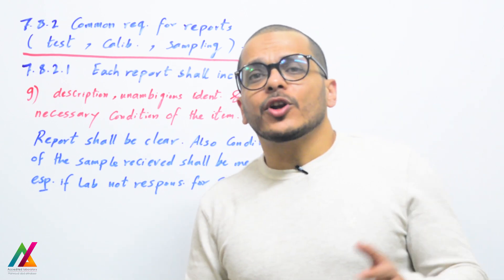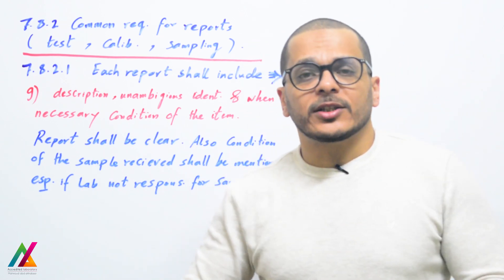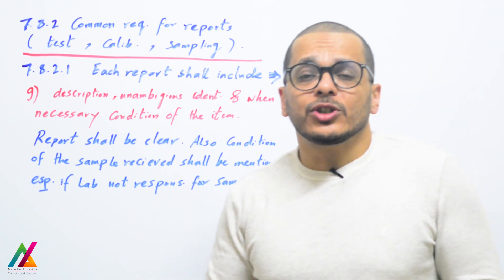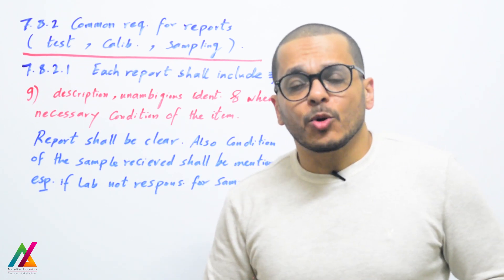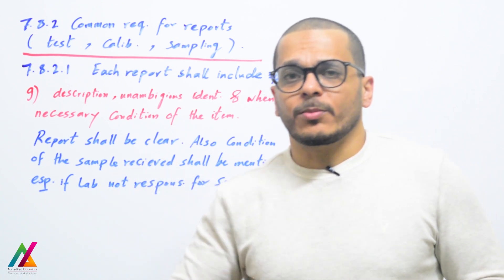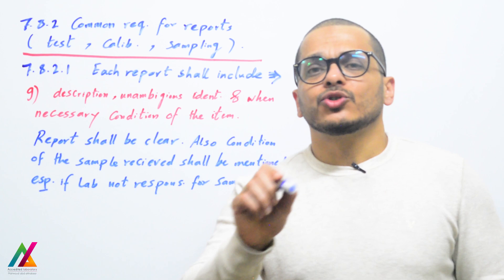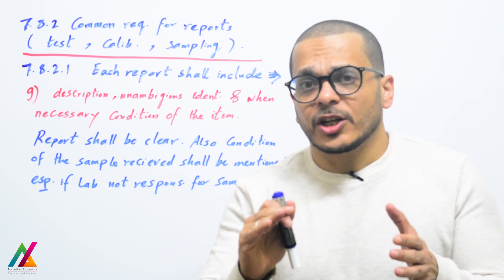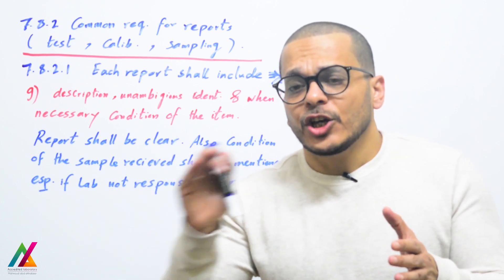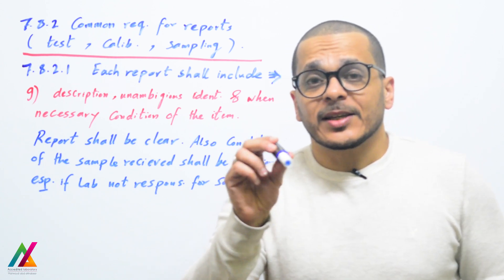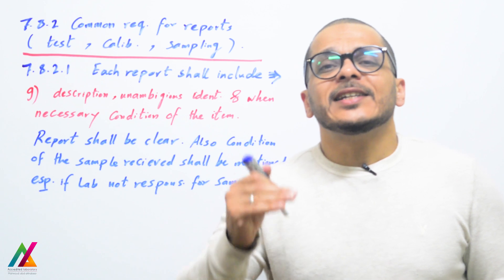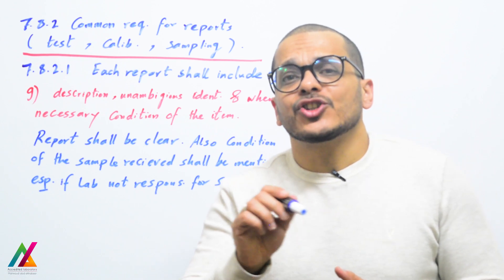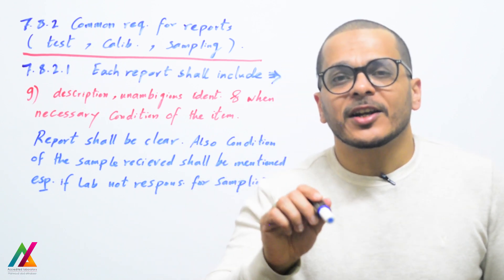The report shall include a description and unambiguous identification of the item, and when necessary, the condition of the sample. The condition of the sample shall be mentioned in the final report, especially if the lab is not responsible for sampling — in which case you state that in the report. If you receive a sample from the customer in a condition that does not meet the required condition, you shall inform the customer that this may affect the validity of results.